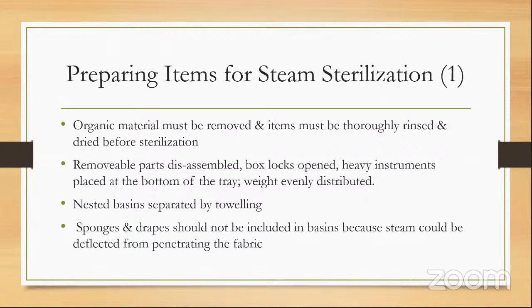Remember and be careful about how we layer instruments on top of each other, because the principle is that the steam must be able to make contact with all the areas of the items that are being sterilized. And if we have instruments lying on top of each other, then that is not going to be a very efficient process. So especially if there are very large items, we have to be very careful about how the instruments are placed in the tray.